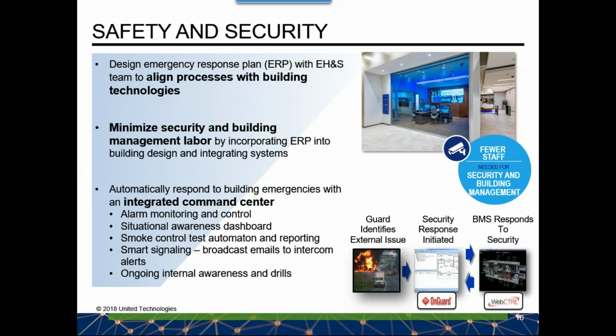We have a security response that the system will do manually - the guard will be notified as to what was sensed, and they'll know what should be done. If they agree, they'll hit a button, and the BAS system will automatically either limit outdoor air intake or do the opposite and increase it if it's a flush. If it's an internally generated contaminant, we'll go to exhaust mode. All these things are automated into the building, and we can do that because of the amount of information we're getting from the building automation systems.